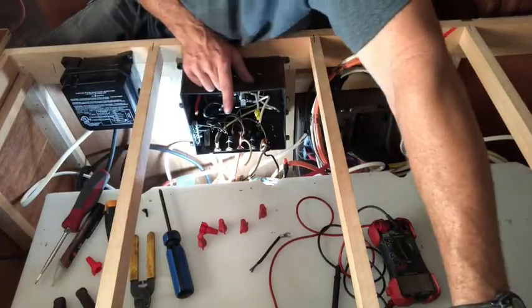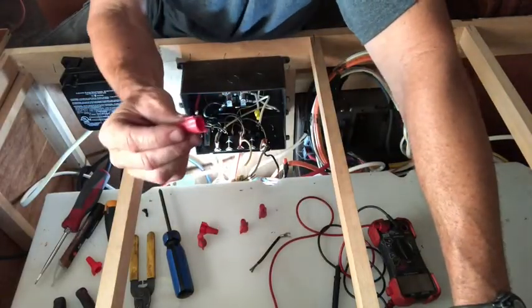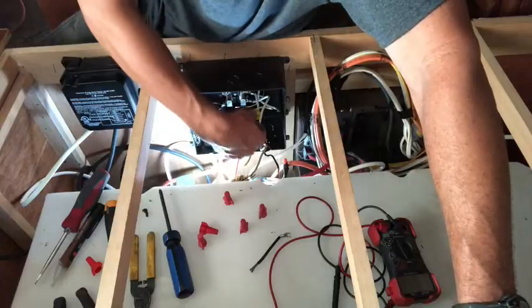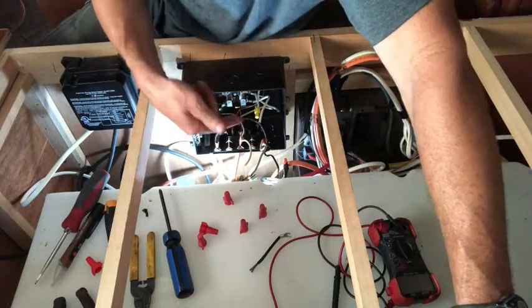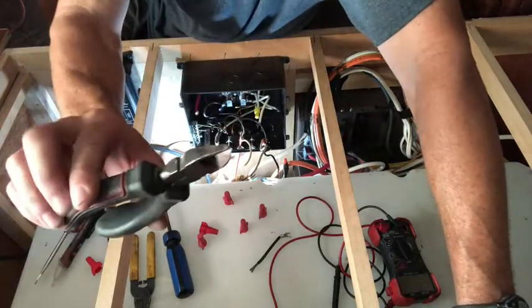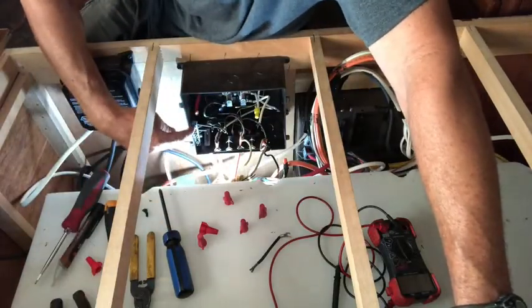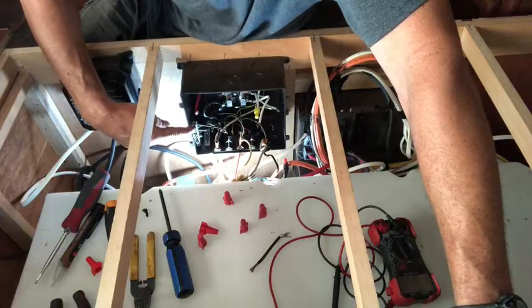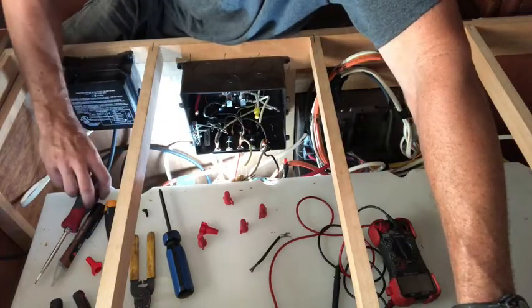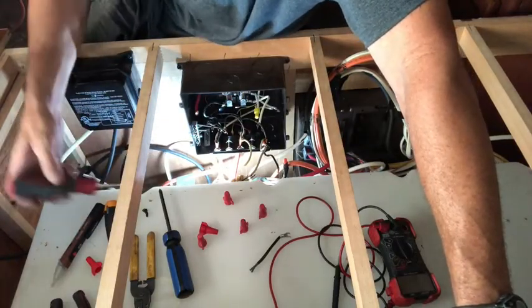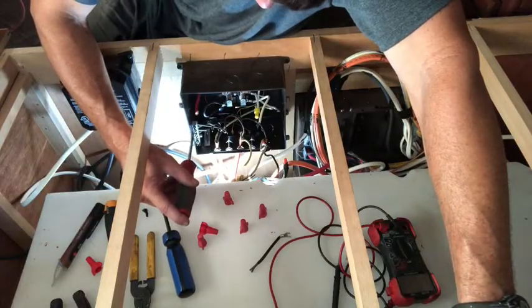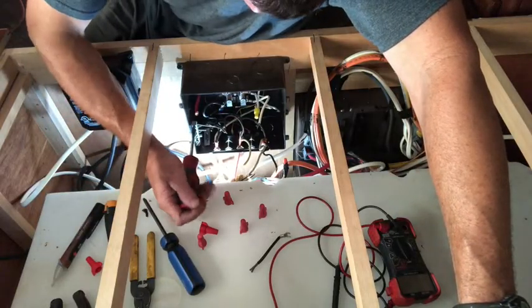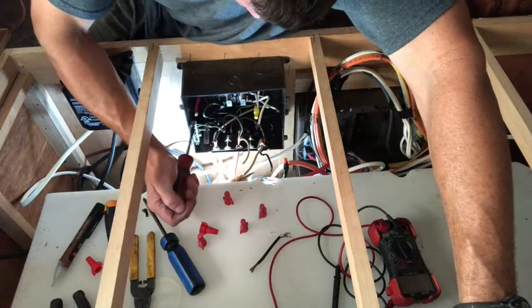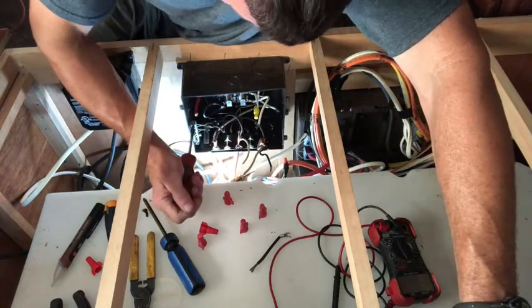On these pigtail style connections, it's mostly pigtails to undo. Every now and then you'll run across a crimp fitting, in which case you have to cut it with a dikes or side cutter. But the grounds are in this ground bus here, clamped by a screw. To get your grounds loose, use a flat-headed screwdriver and loosen that screw so you can get those wires out.